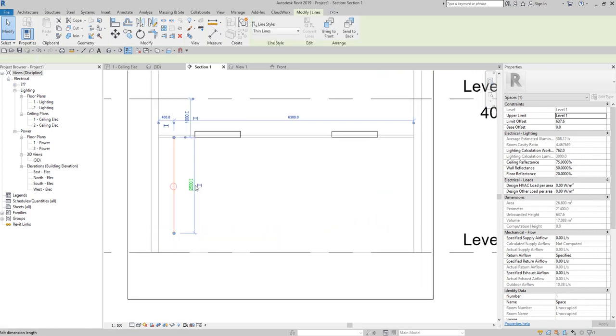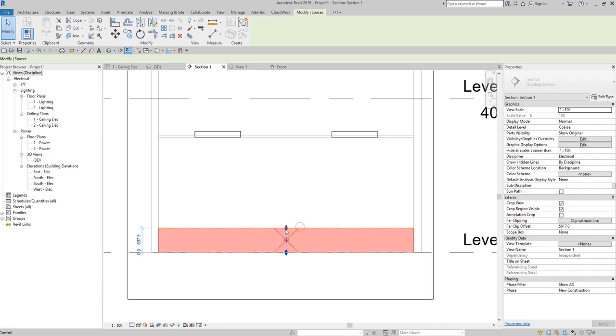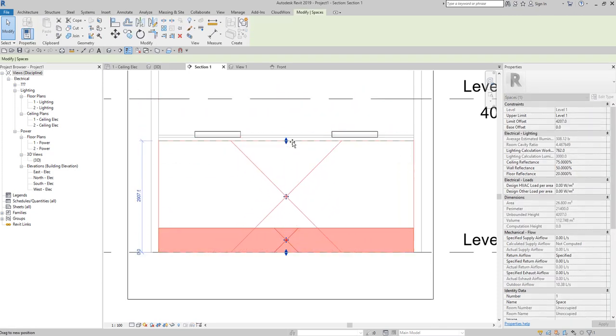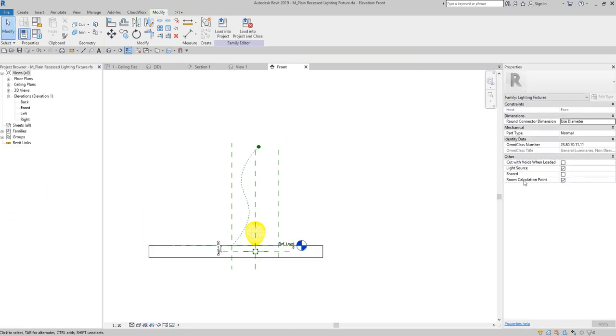So you have two ways of solving this problem when designing electrical layouts. Either you pull down or pull up your space so that it touches the fixture and reads the average estimated illumination, or you edit the family and adjust the room calculation point. Just enable that option and play around with the room calculation point. Hopefully you learned something from this video. If you have any comments, questions, or suggestions, put them in the comment section below. Thank you for watching, guys — have a nice day!